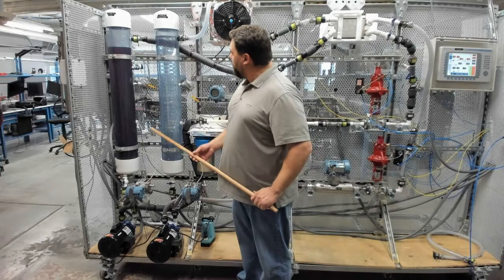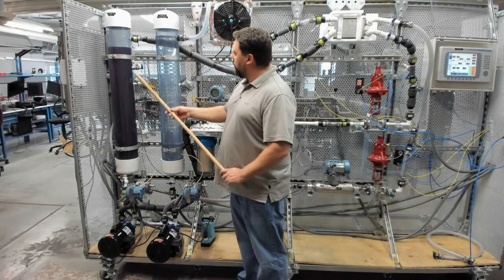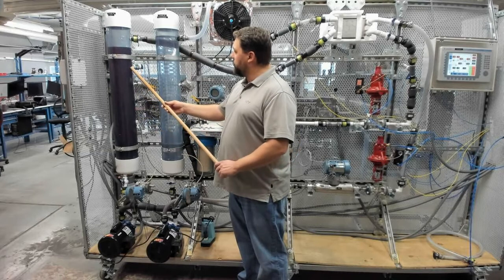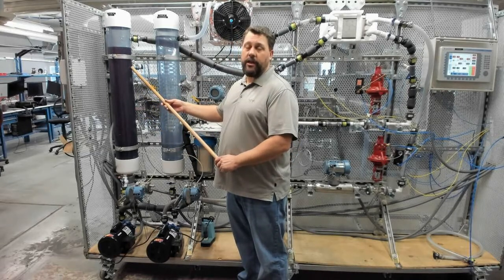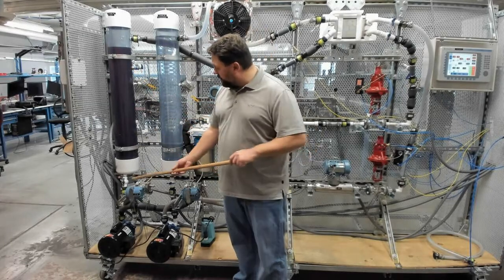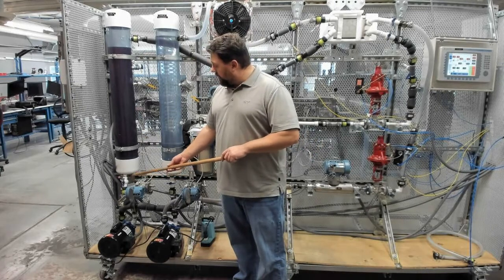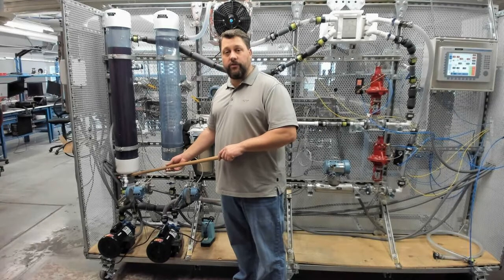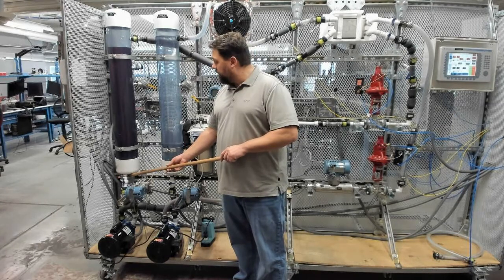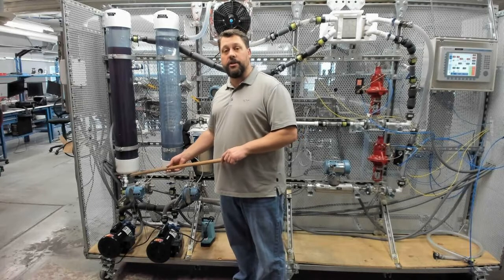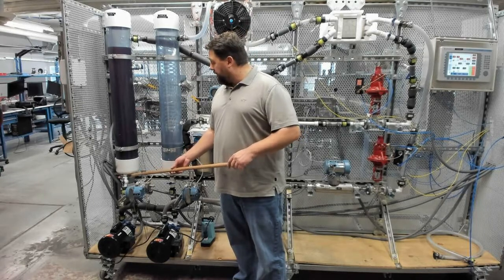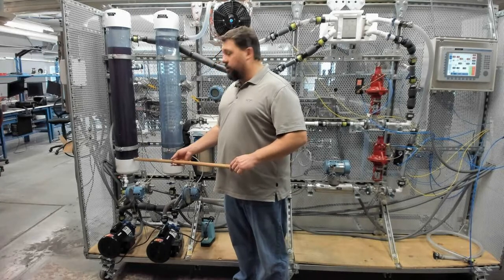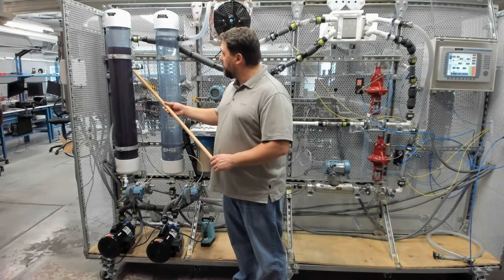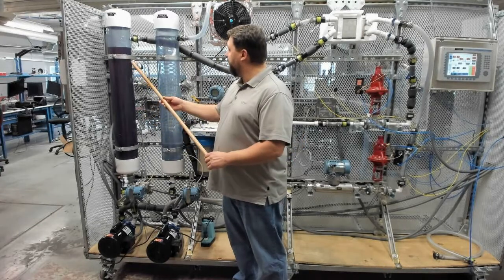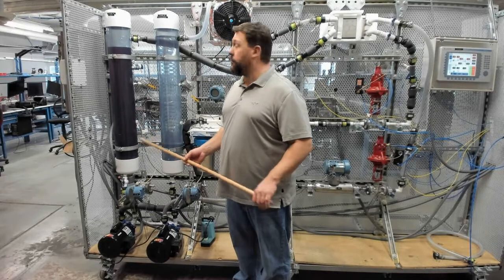The level controls, or these level switches, and this temperature switch are installed so we can ensure that there's the proper amount of fluid in the tank. There's a heating element in the bottom of this tank down here. If we didn't have heat transfer fluid in there, the fluid could get too hot, and we could damage the heating element. We could damage the PVC. There's a number of things that could go wrong. So we have a temperature switch in here that acts as a safety, and then the switch is here. So that's part of your motor control scheme to ensure safety there.